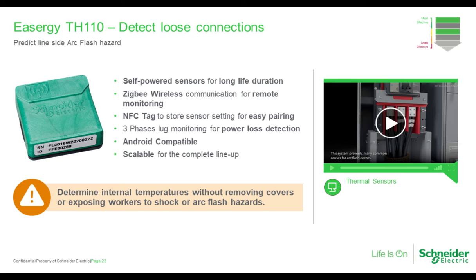There's one sensor per phase, as you can see. They are self-powered using the bus connections and the ribbon. Innovative solution that's attached to the back of the sensors. It being self-powered eliminates the need to replace batteries, have to go into the ArcBlok periodically. And they're all equipped with wireless Zigbee communications, which makes the thermal readings available on our free Thermal Connect app. So you would use your phone to collect the data instead of the traditional method. So it provides a more quick, convenient way to view the temperature data in a way that minimizes exposure to live parts, and it helps personnel be outside of the arc flash boundary area.